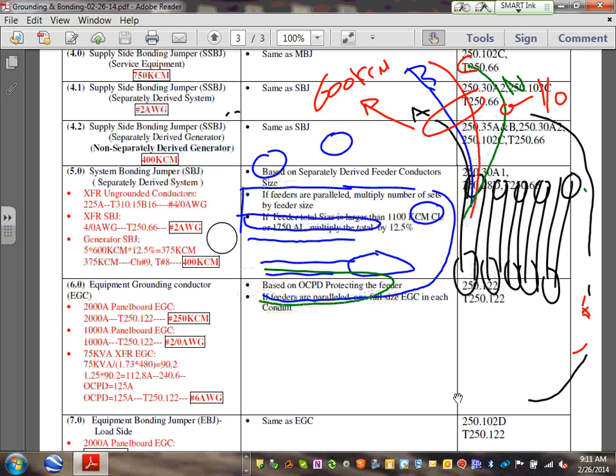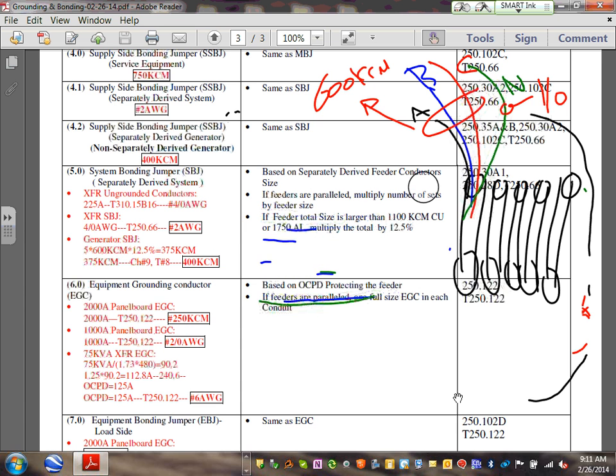So here's my 5.0. I'm going to leave these conduits with me, carrying these conduits with me wherever I go here. 5.0. This is at the generator, so I need to focus on this one because I need to look at the generator. Do you guys remember that 6 conductors here? 600 kcm, 5 conductors? Everybody can see that? So I take 5 because I have 5 sets, multiplied by 6 conductor, 600 kcm, because each one of them is 600. You multiply by 12.5% because they're more than 1100 kcm. That will get you 375 kcm.